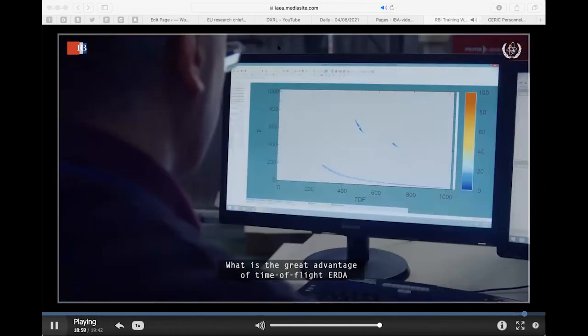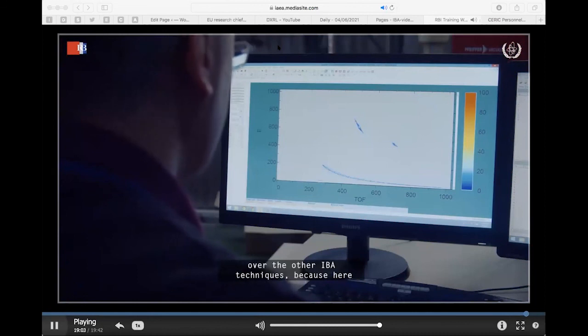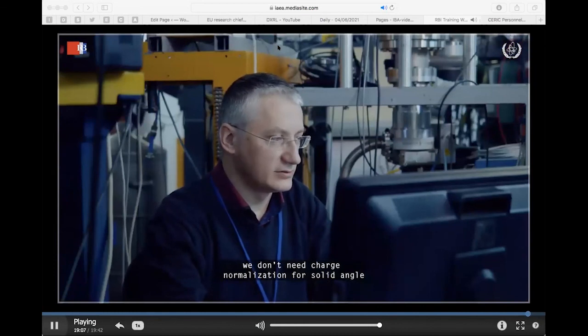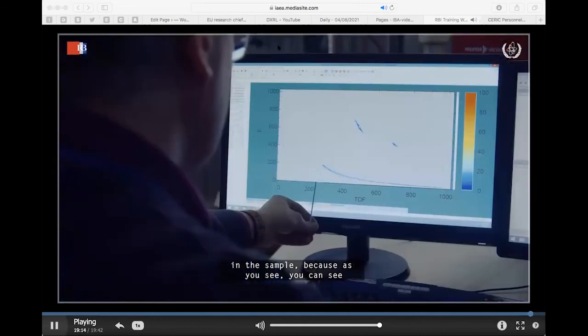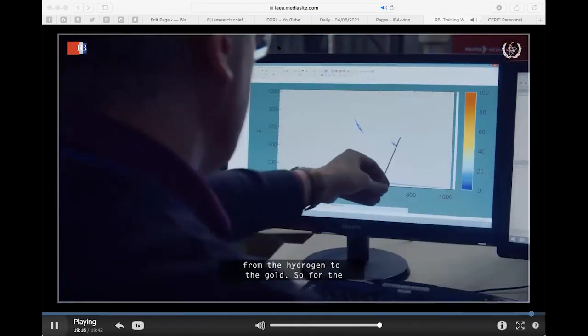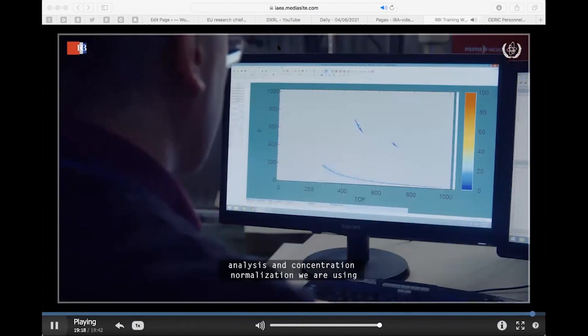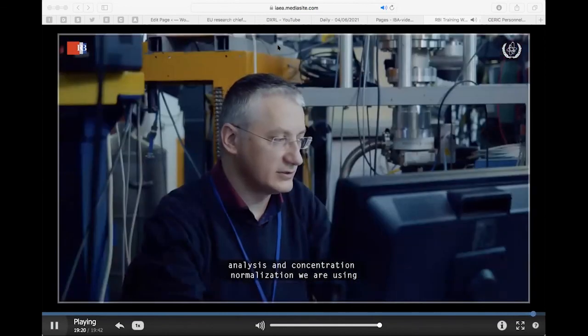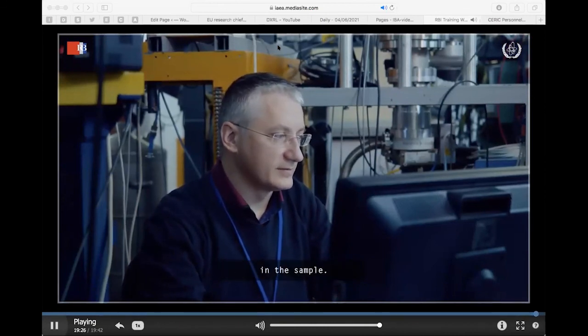What is the great advantage of time-of-flight ERD over the other IBA techniques? Here we don't need charge normalization or solid angle normalization, because we see all the elements present in the sample. As you see, you can see from hydrogen to the very gold. So for the analysis and concentration normalization, we are using 100% normalization to the total elements present in the sample.